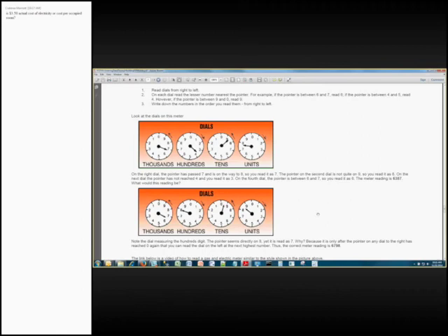So another thing I should mention, I know I mentioned these dials are common on gas meters. On many gas meters, you may see two dials, one that says temperature compensated and one that says temperature non-compensated. You always do the non-compensated. Opposite. You always do the temperature compensated. I apologize, the other way around. Always read the temperature compensated value. That's the one you're going to want to take when reading from a gas meter.